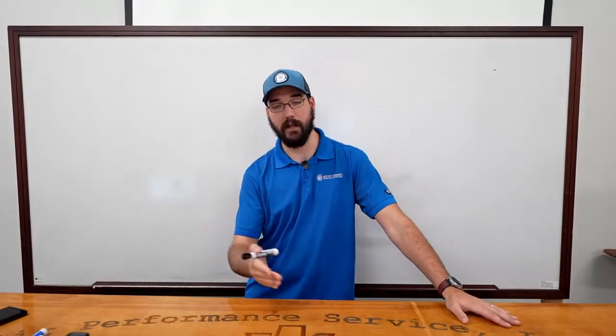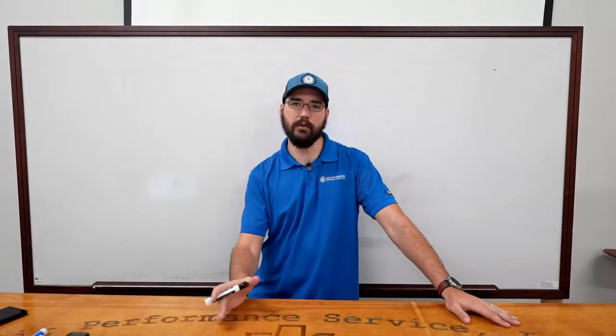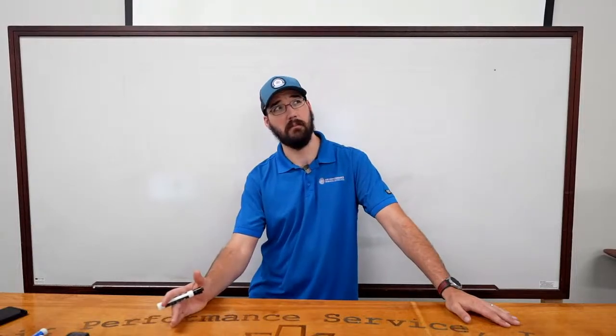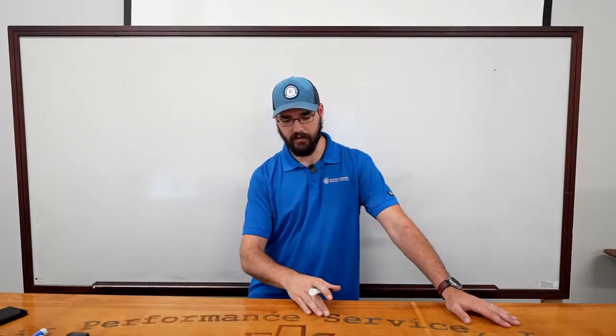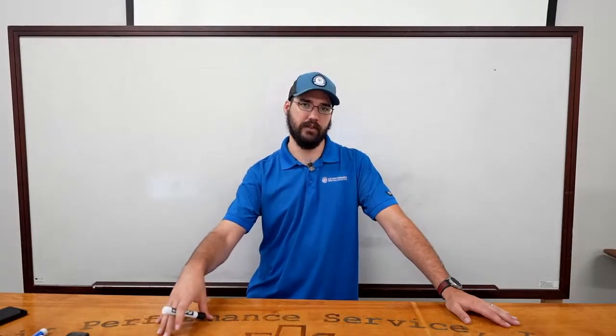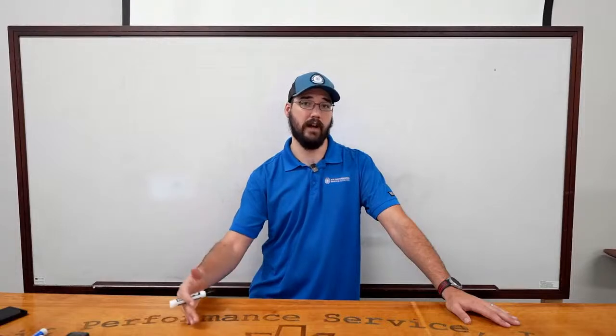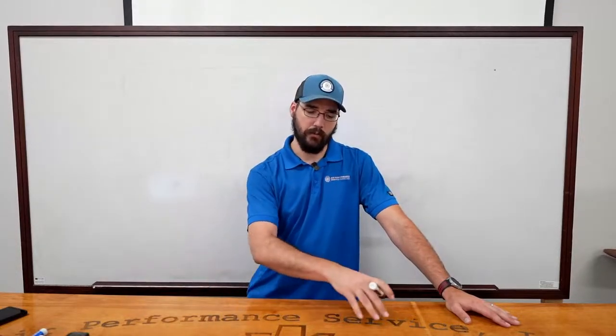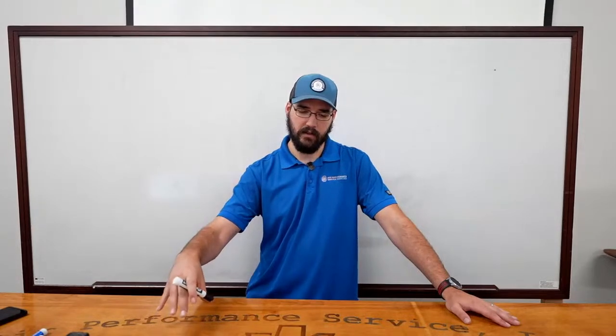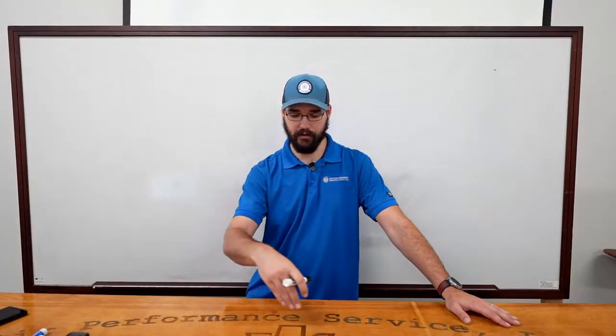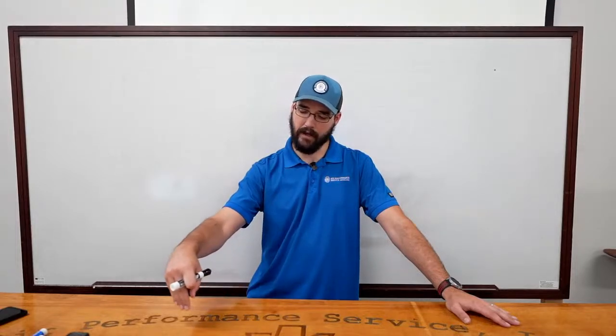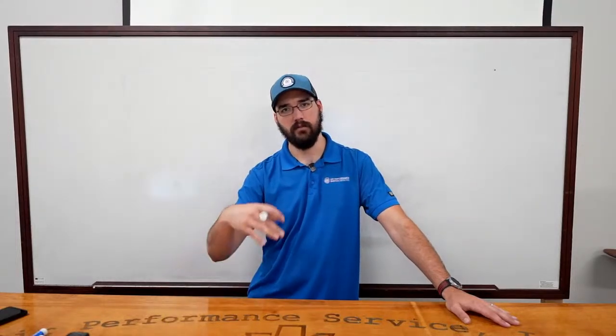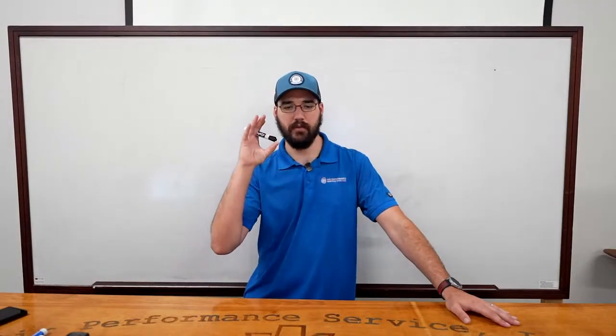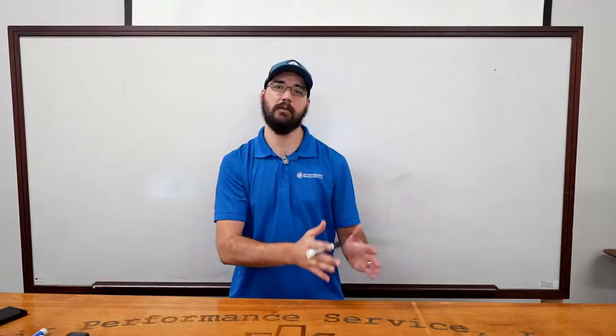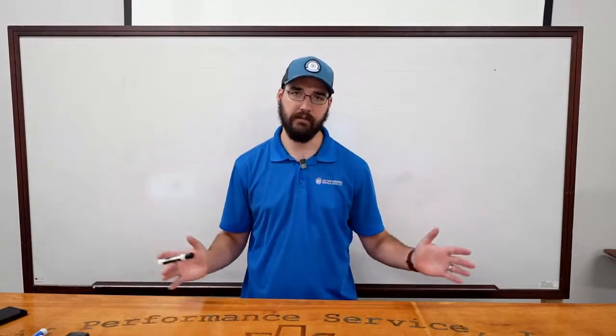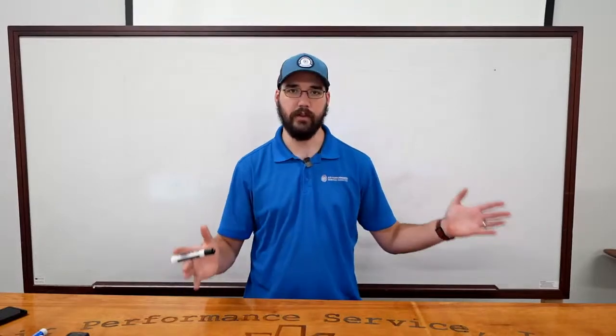But you have to go, for Daikin for example, and even LG, into the service mode, which for Daikin is considered mode 2 or mode level 2. And then you have the function menus for the LG side where you tab, dip switch 5, and you can go through all those. So a lot of the troubleshooting, if you have the alarm code and if you have the manual, you should be good. And really try to go as far as you can. If you have the laptop readily at hand, that's fine. Forget everything I'm saying. Just go ahead, use it.